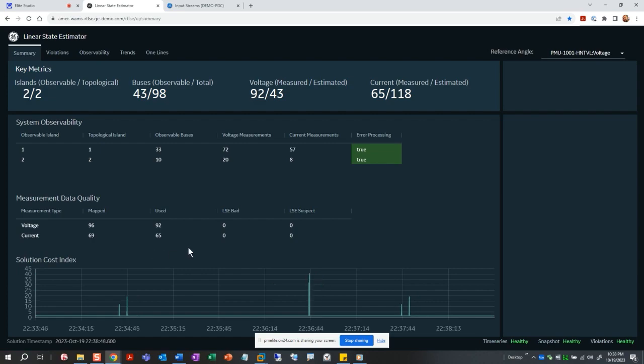And like Manu had already mentioned, it's a linear state estimator because it's already measuring the actual state of the grid. It's measuring the magnitude and angles on the grid. And so it reduces the whole state estimation solution down to just a linear algebraic problem. And so that's why we're able to solve it at such a rapid speed.